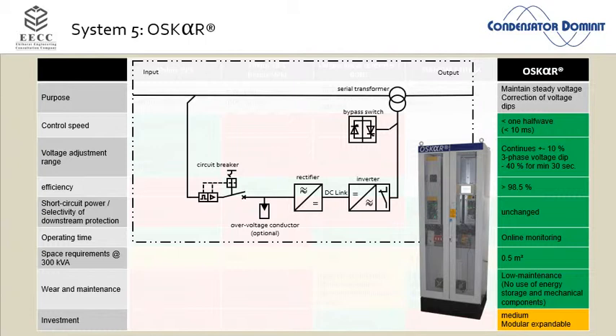The first OSKAR we built as fast as possible. And that was a big mistake, because if you have something that's too fast, it's not stable anymore. What we learned doing that is, if we make our system the fastest we can, we create trouble, because then you switch a capacitor bank here, or some machine equipment, and your system is so fast that it starts to interact with your load. So we had to artificially slow down the power electronics. A lot of people ask me how fast your system is. The maximum time we measure is 2-3 milliseconds, till the correction is finished.